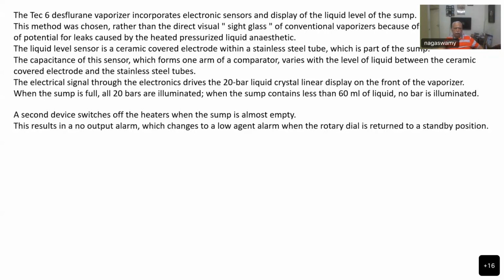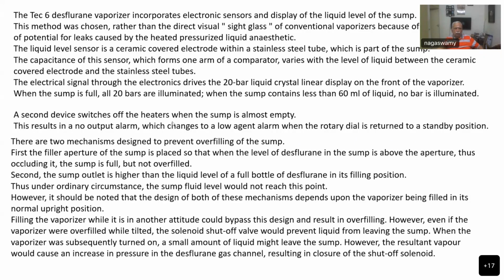So the method of activating the no output alarm is by switching off the heaters, which changes to a low agent alarm when the rotary dial is returned to a standby position. And there are two mechanisms designed to prevent overfilling of the sump. On other vaporizers, there is a possibility you can overfill the sump.